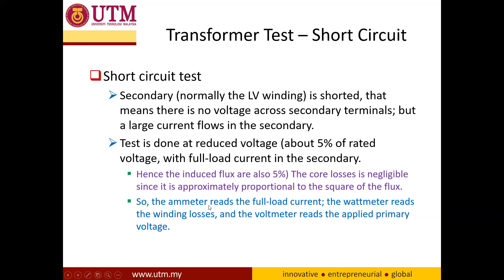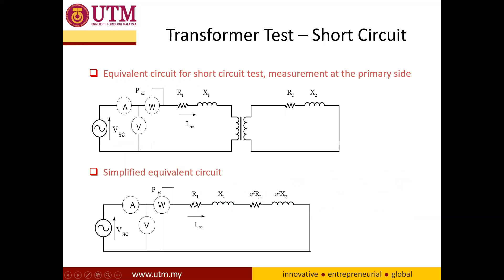The ammeter reading, voltage reading, and power reading will represent the internal resistance of the winding and also the leakage inductance. To simplify the calculation, we transfer all the secondary parameters into the primary. R1 and a² times R2 combine to form R equivalent 1, while X1 and a² times X2 combine to form X equivalent 1.